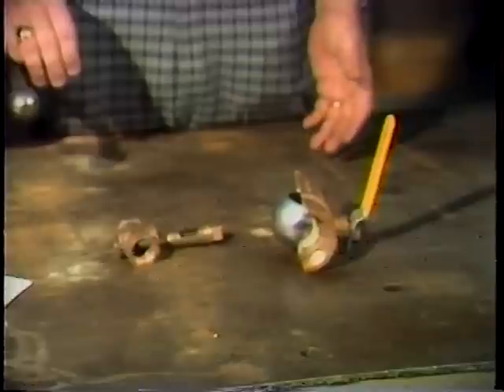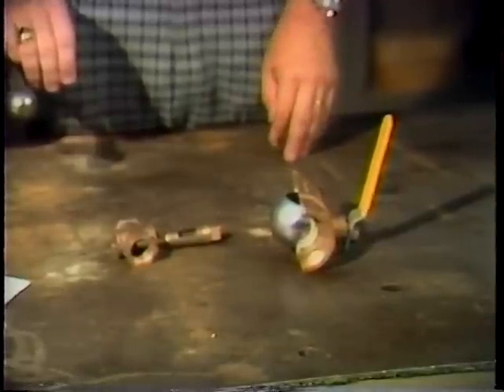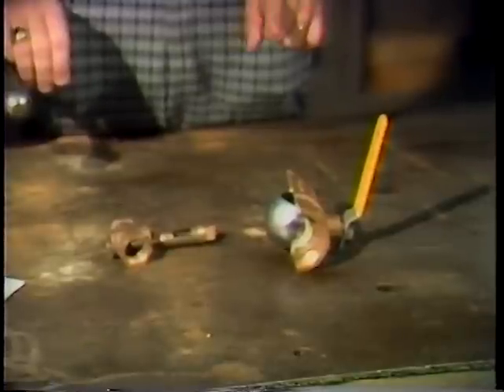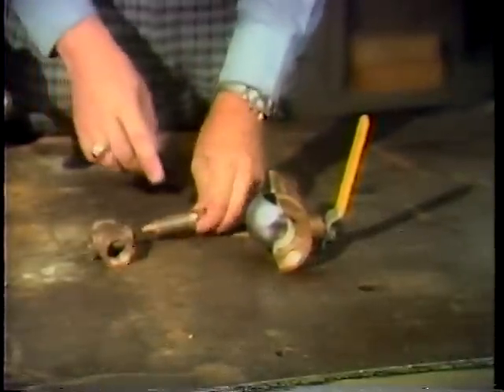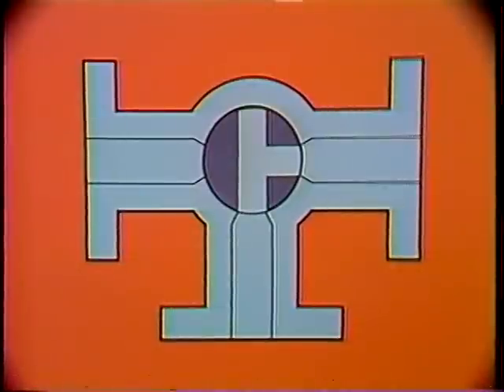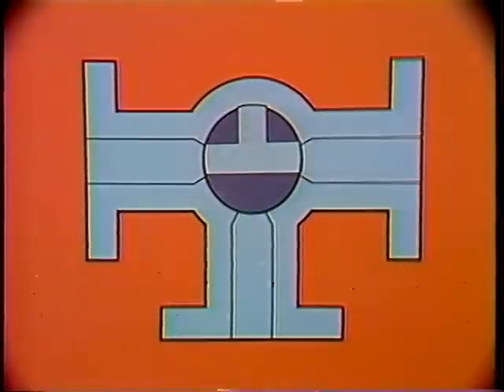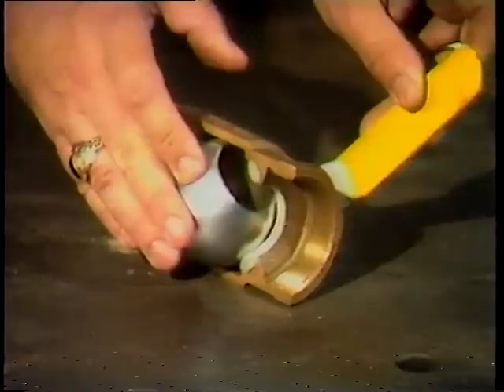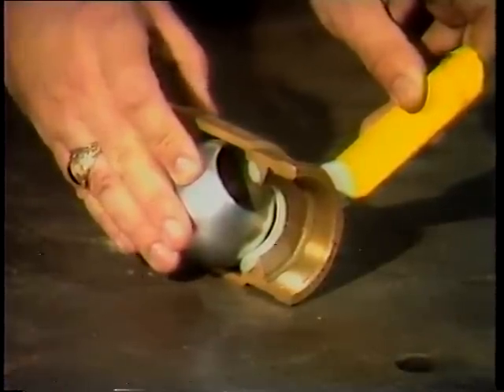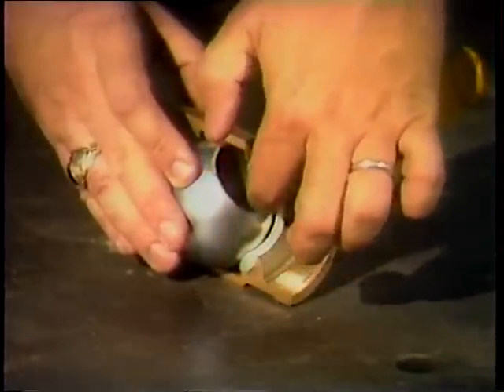Usually this design does not provide the same tight sealing quality of the globe valve, but these valves aren't generally used in systems requiring a tight shutoff. Often you'll see plug and ball valves on lubricating systems, such as on a duplex strainer. A plug or ball valve can be single port or a multi-port valve. Here is a three-way, three-port plug valve with three different flow paths available. But if the valve is not lined up to allow full flow, a throttling action will take place — it's not good to let that happen because the fluid will put pressure on the seals around the disc as it is throttled.